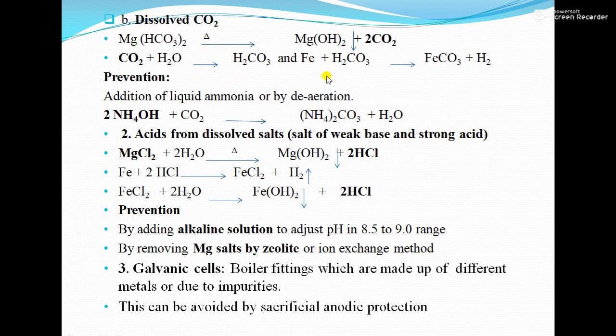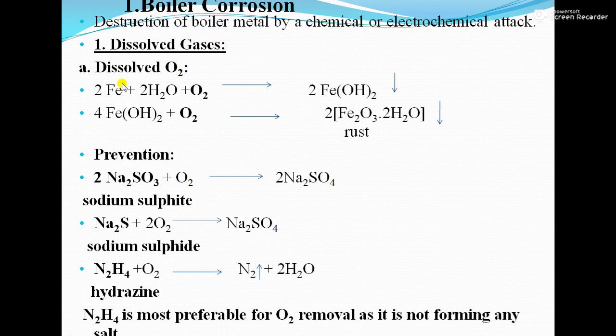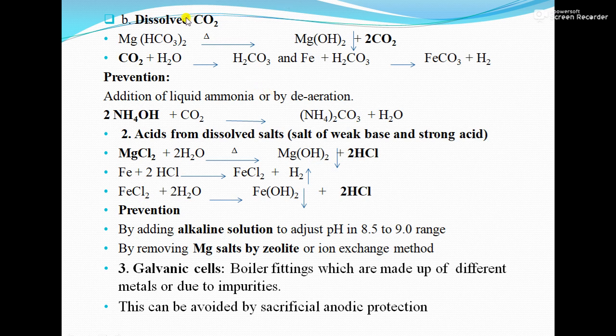To prevent corrosion due to CO₂ and temporary hardness, we add liquid ammonia or use de-aeration. Adding ammonium hydroxide converts the CO₂ present in the water into ammonium carbonate, and in that way corrosion is reduced.